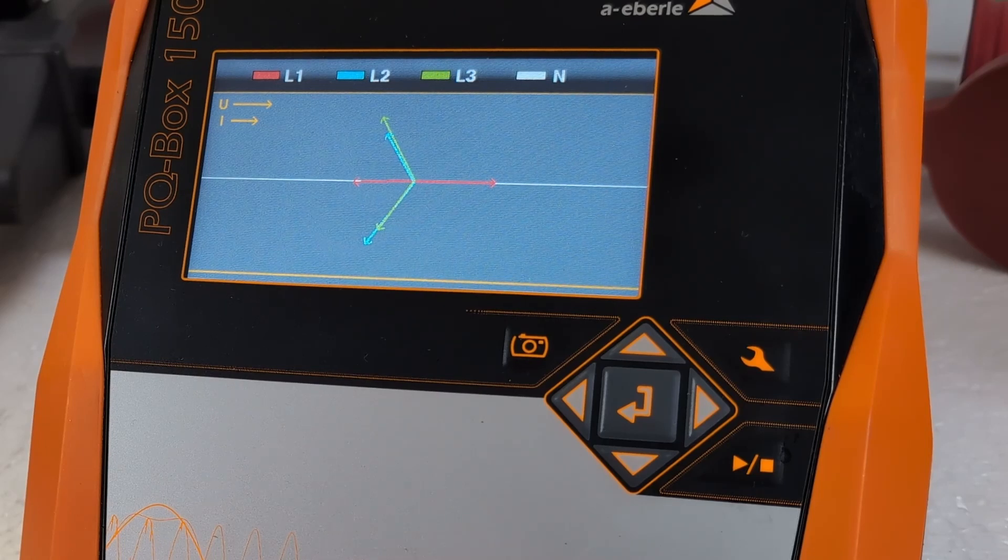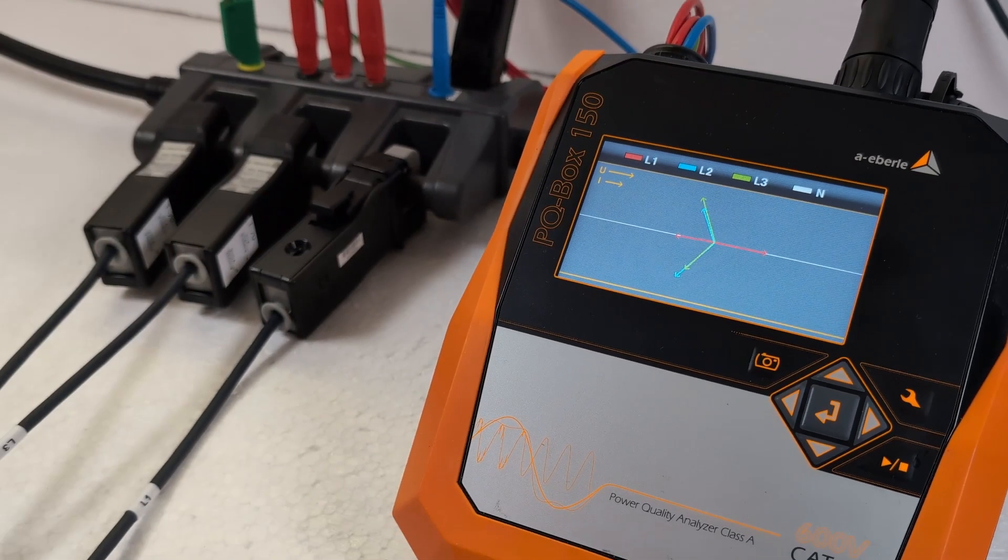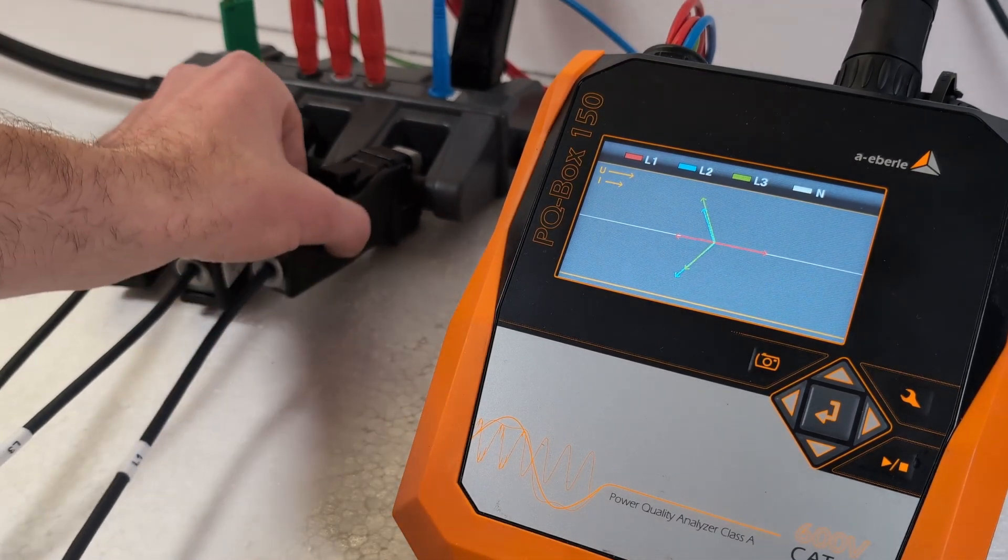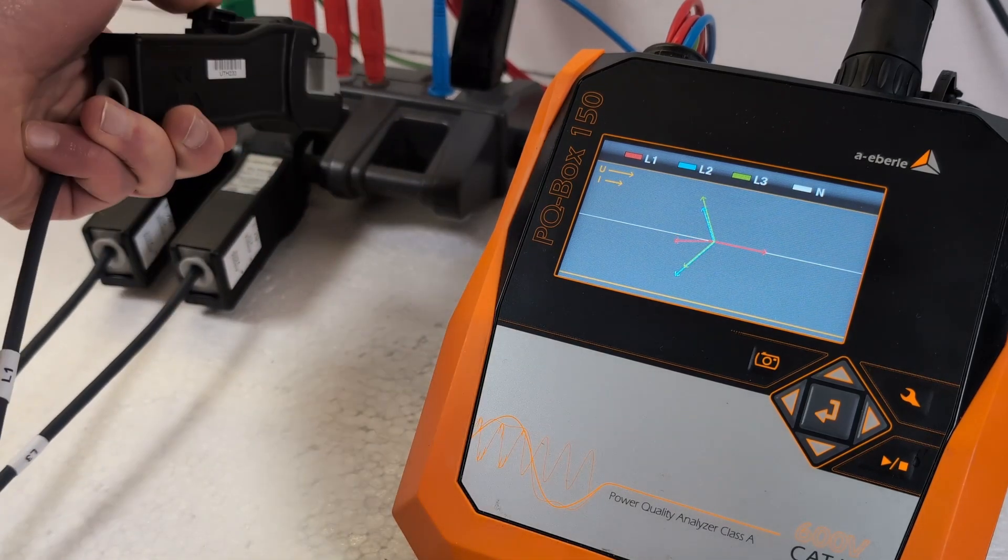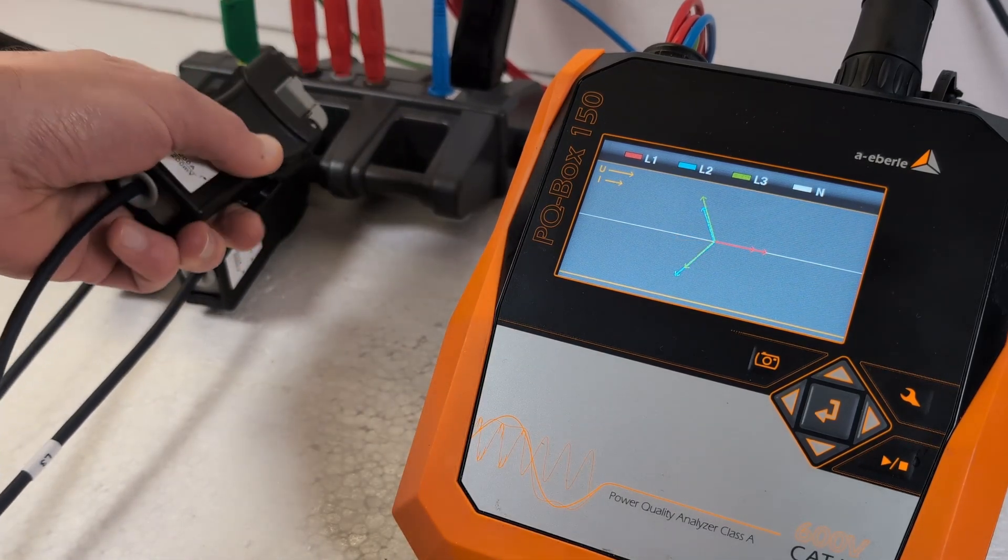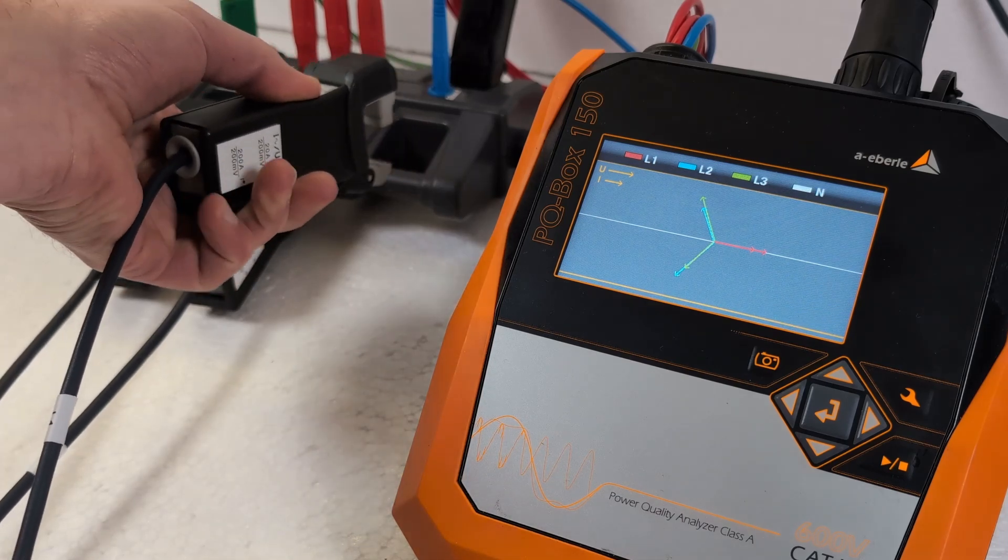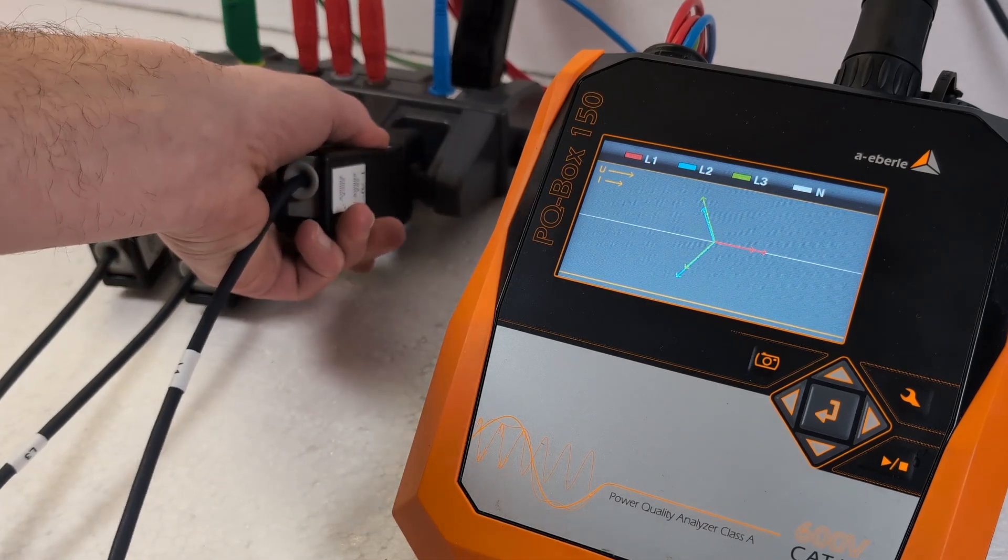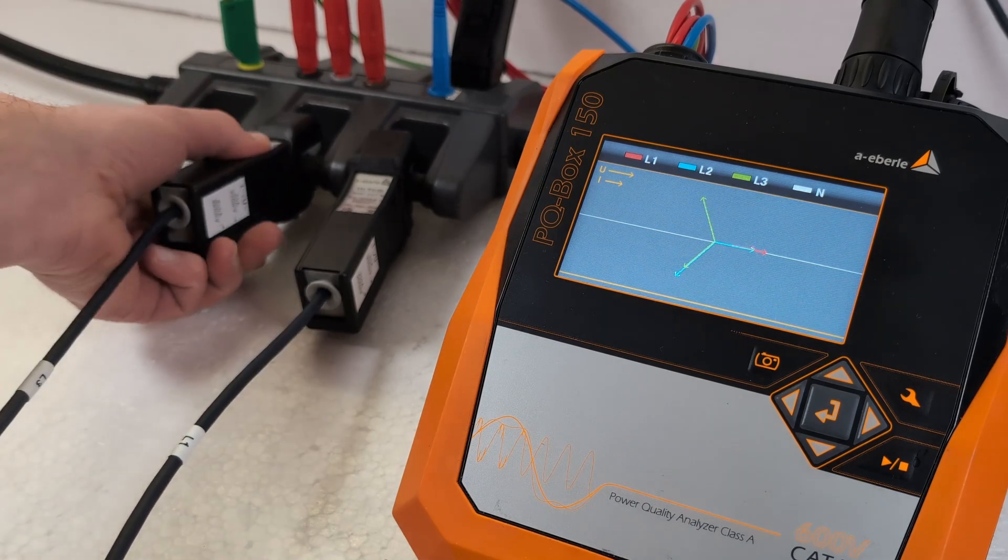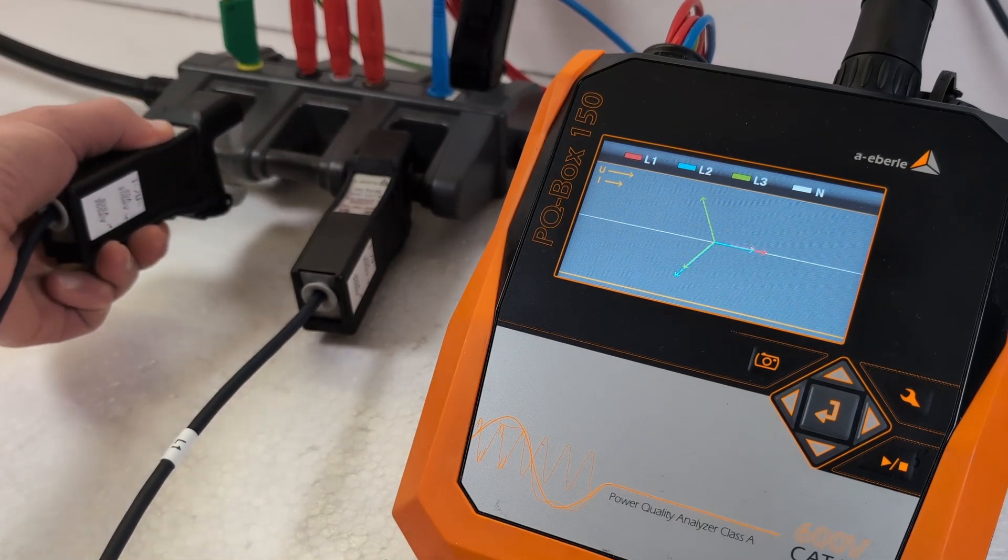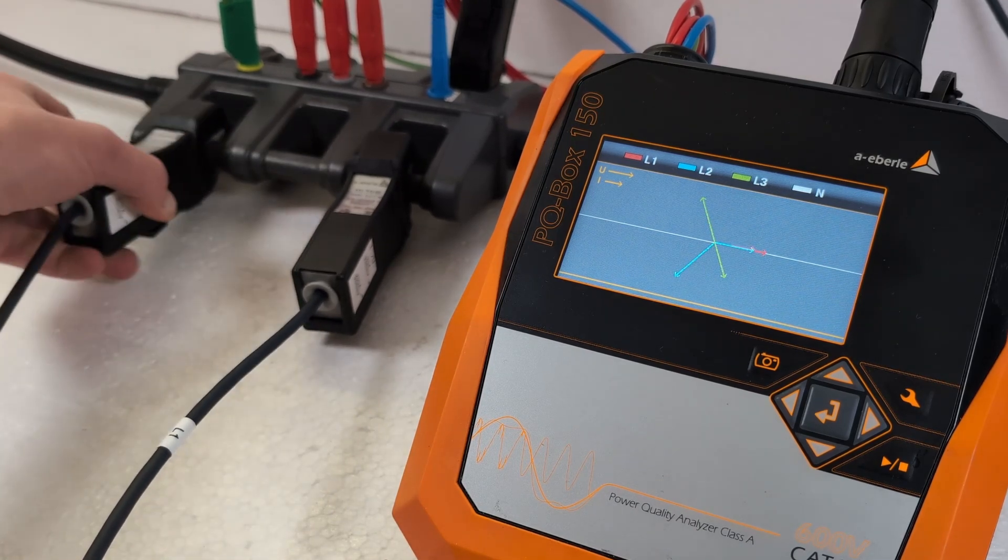I have deliberately done something wrong here when connecting the current clamps. Red is rotated by 180 degrees. So I connect the current clamp L1 the other way round. I also swap the current clamps L2 and L3 so that the green and the blue pointers match.